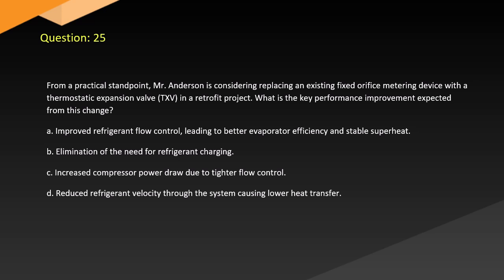Question 25. From a practical standpoint, Mr. Anderson is considering replacing an existing fixed orifice metering device with a thermostatic expansion valve (TXV) in a retrofit project. What is the key performance improvement expected from this change?